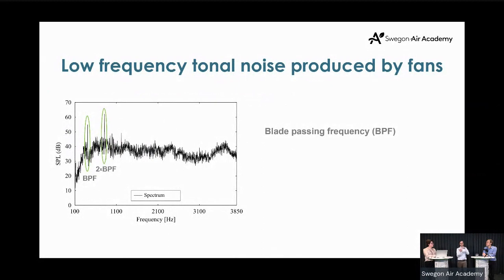The blade interaction between the guide vanes and the volute cutoff generated this blade pass frequency tone. But we removed this casing or volute a long time ago in the industry, and we still have this tone. Until my study, there was no real source developed, or they hadn't found the real sources. So that's why I started my study on this.